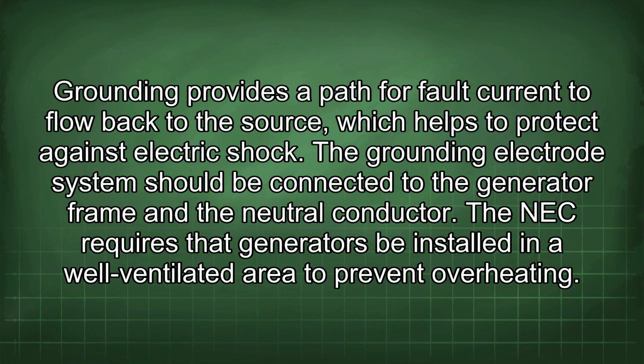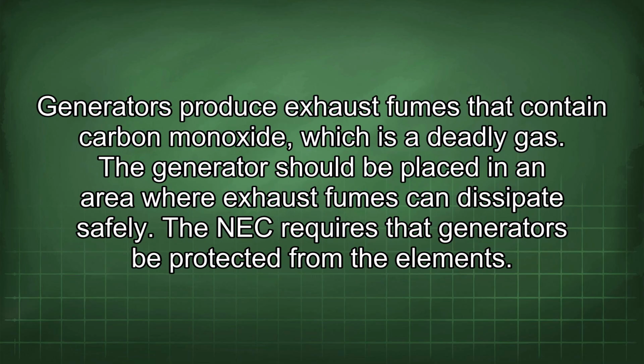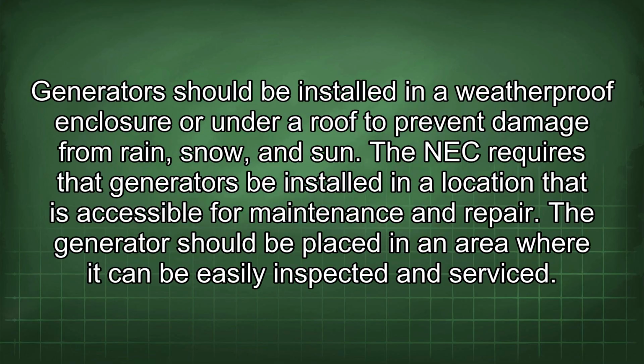The NEC requires that generators be installed in a well-ventilated area to prevent overheating. Generators produce exhaust fumes that contain carbon monoxide, which is a deadly gas. The generator should be placed in an area where exhaust fumes can dissipate safely. The NEC requires that generators be protected from the elements. Generators should be installed in a weatherproof enclosure or under a roof to prevent damage from rain, snow, and sun.